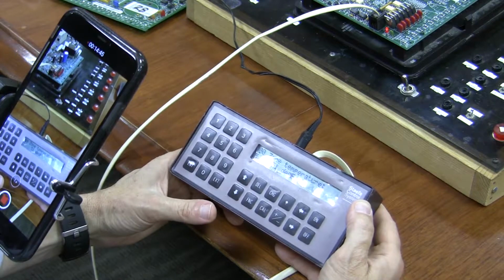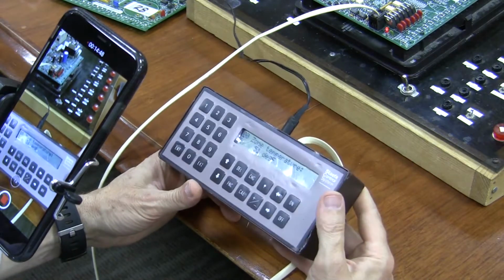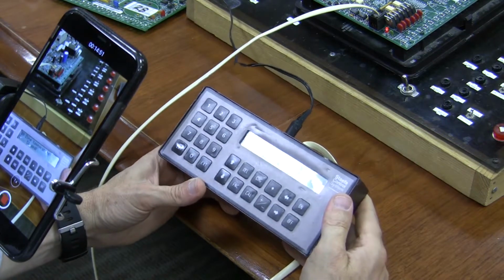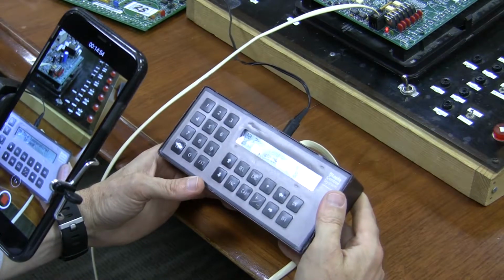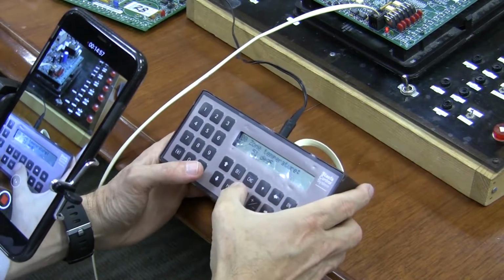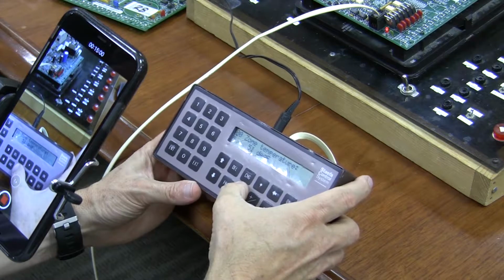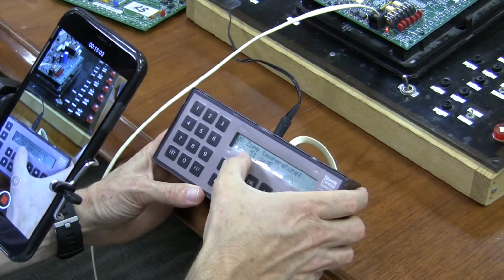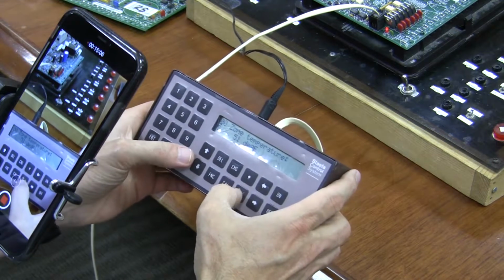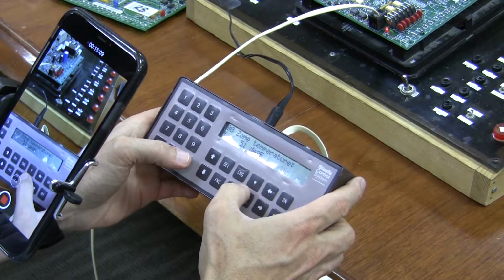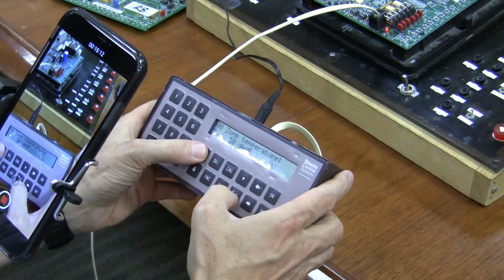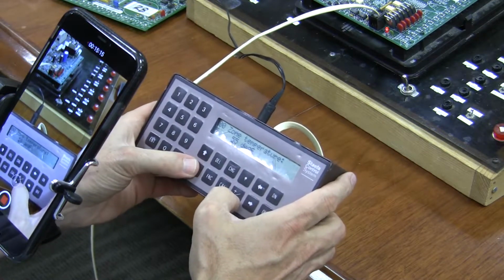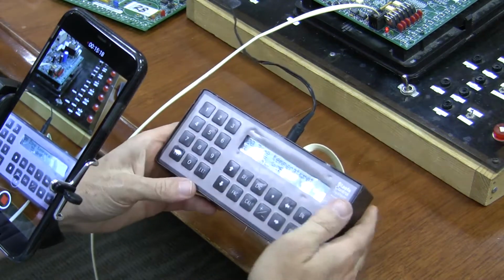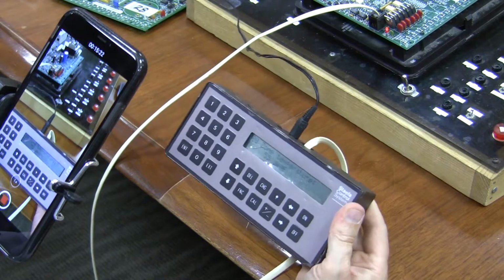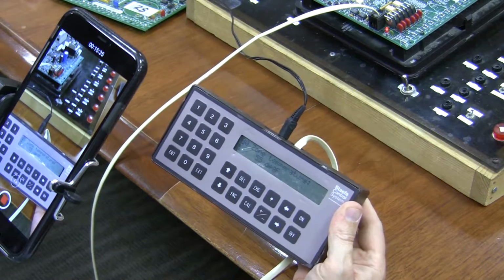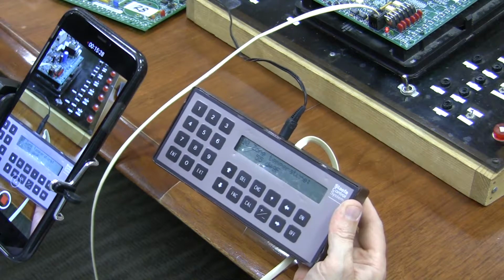Okay? So that's something that I may want to do, is to calibrate that zone sensor. I'm measuring 70 degrees, but when I plug in, parameter number 00 is saying 72. Okay, in this particular case, we're reading 51 degrees, because he's not really wired up to anything, but I'm going to show you how I'd calibrate it. So I could hit the calibrating button. I couldn't do it unless I see the little CL. The CL comes from being in commissioning mode. Okay, so I'm going to hit the cal button. And now I'm going to scroll, and I'm going to say, no, I really think it's 55 in here. And then I'm going to hit enter, and now I just calibrated that zone sensor. And I just added 4 degrees. In this particular case, I took it from 51 to 55.